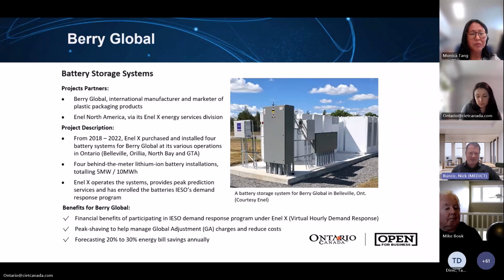Looking at the first example, we have an energy storage system with Berry Global International, a manufacturer and marketer of plastic packaging products. The partners in this project are Enel North America, an Italian company, via its Enel X energy services division. The project involved the purchase and installation of battery energy storage systems at Berry Global's four locations in Ontario: Belleville, Orillia, North Bay, and the GTA. Four behind-the-meter lithium-ion battery installations totaling 5 megawatts of output capacity and 10 megawatt hours of storage capacity. Enel operates the systems, provides peak prediction services, and has enrolled the batteries in IESO's demand response program.